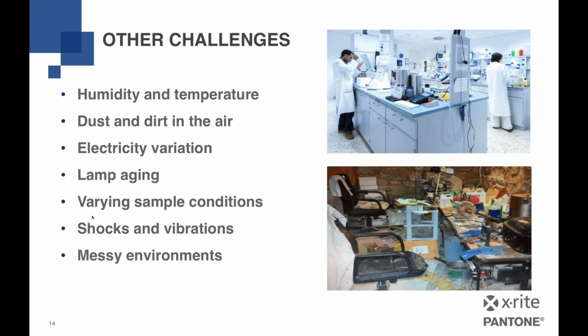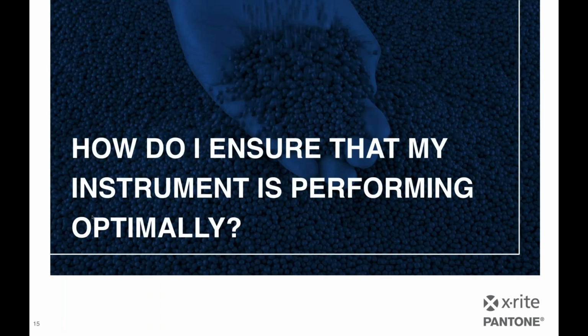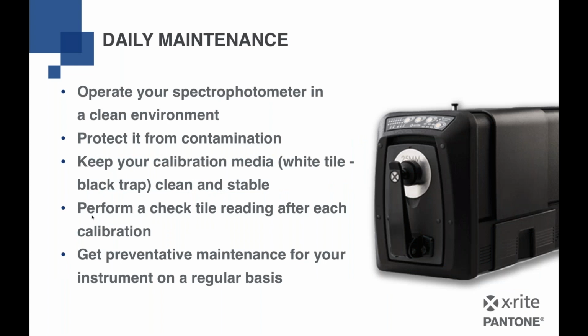And of course, messy environments never help to sustain good readings, as these two contrasting pictures show. So how do I ensure that my instrument is performing optimally now? We would consider some things as daily maintenance. You should operate your instrument in a clean environment. You should definitely protect it from contamination. We actually have customers who wrap their instruments partly or fully in foil sometimes to protect it from contamination.